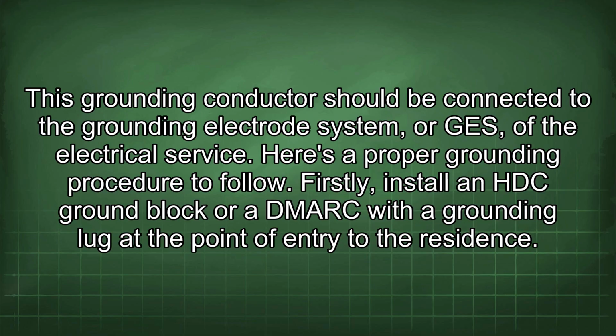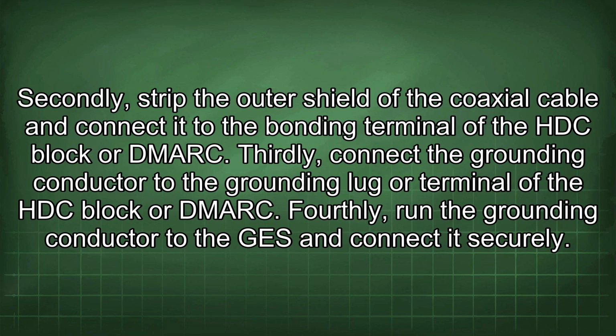Here is a proper grounding procedure to follow. Firstly, install an HDC ground block or a demarc with a grounding lug at the point of entry to the residence. Secondly, strip the outer shield of the coaxial cable and connect it to the bonding terminal of the HDC block or demarc. Thirdly, connect the grounding conductor to the grounding lug or terminal of the HDC block or demarc. Fourthly, run the grounding conductor to the GES and connect it securely.